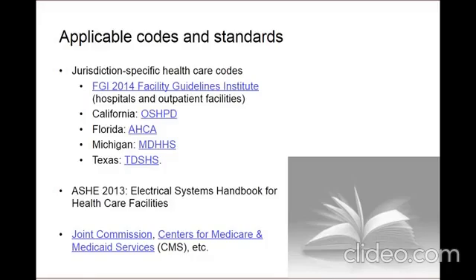The FGI guidelines, or state-specific codes, depending on where you're at, include many of the same or similar requirements as NFPA 70 and 99. However, they are also much more specific on the code requirements within each department of a hospital. The guideline is specifically divided up into departments you would expect to find within a hospital, such as surgical suites, patient rooms, emergency departments, imaging suites, and so on. And each one has their own abundance of requirements, such as the quantity of receptacles, light switching requirements, nurse call requirements, the list goes on.